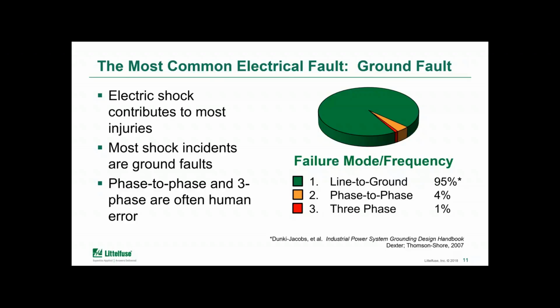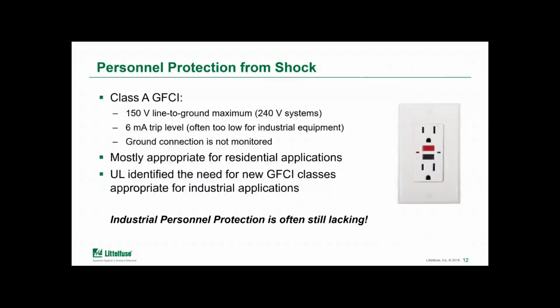Now, it's not to say that a phase-to-phase or a three-phase fault never occurs, but in many cases they do escalate from ground faults, and only about 5% of electrical faults are not initiated by ground faults. And in those cases, the root cause can be miswiring, accidental shorting, or human error, which would typically be some of the major drivers. Now, one type of ground fault is when a person, perhaps standing on the ground or touching something that's electrically bonded to ground, comes into contact with an energized phase conductor.